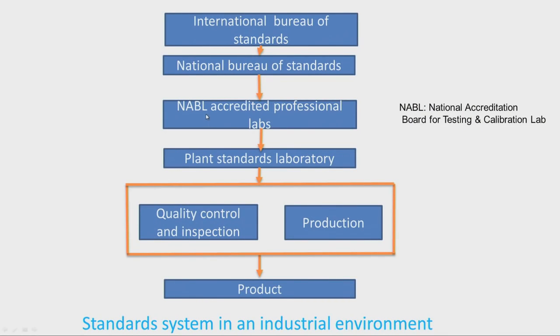While preparing the inspection report, we should note the error indicated on the instrument. The plant standards laboratory equipment should then be compared with equipment at NABL accredited professional labs, which are of superior quality. In turn, the accredited professional labs' instruments are compared with national bureau of standards. This way all measuring instruments are compared with higher accuracy instruments in a step-by-step manner.